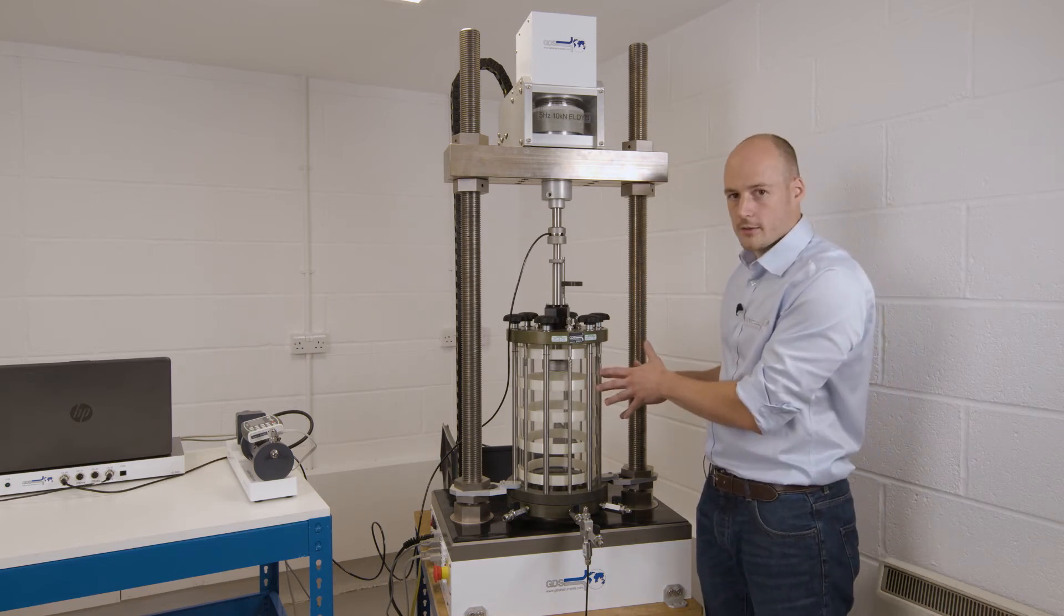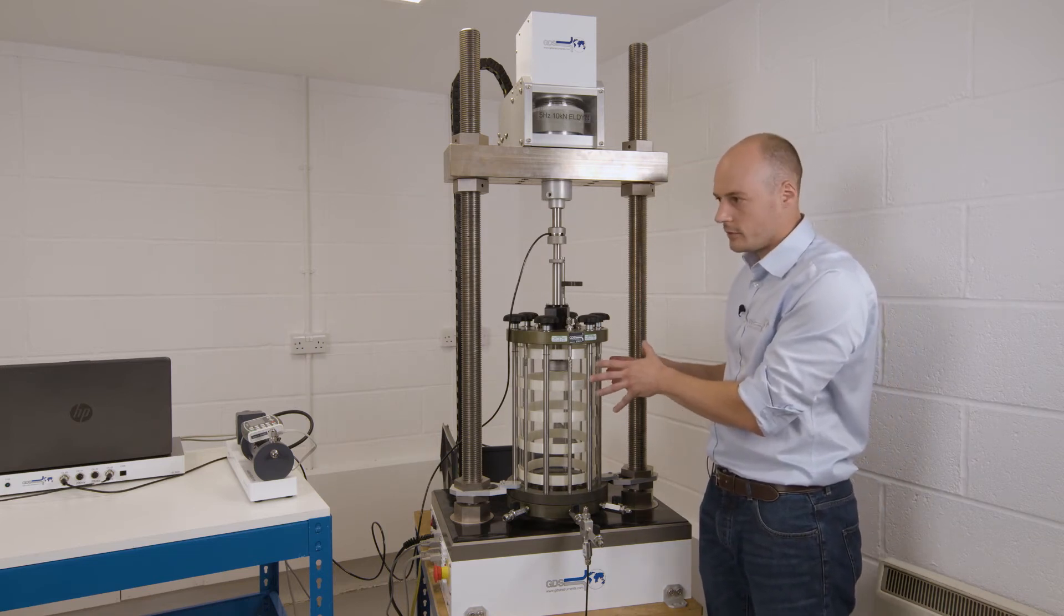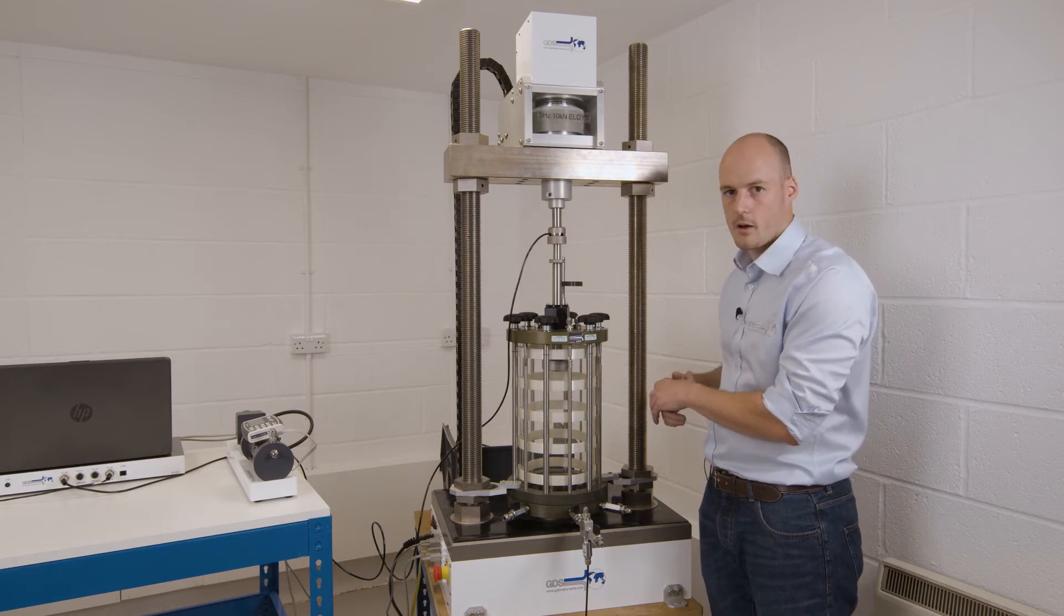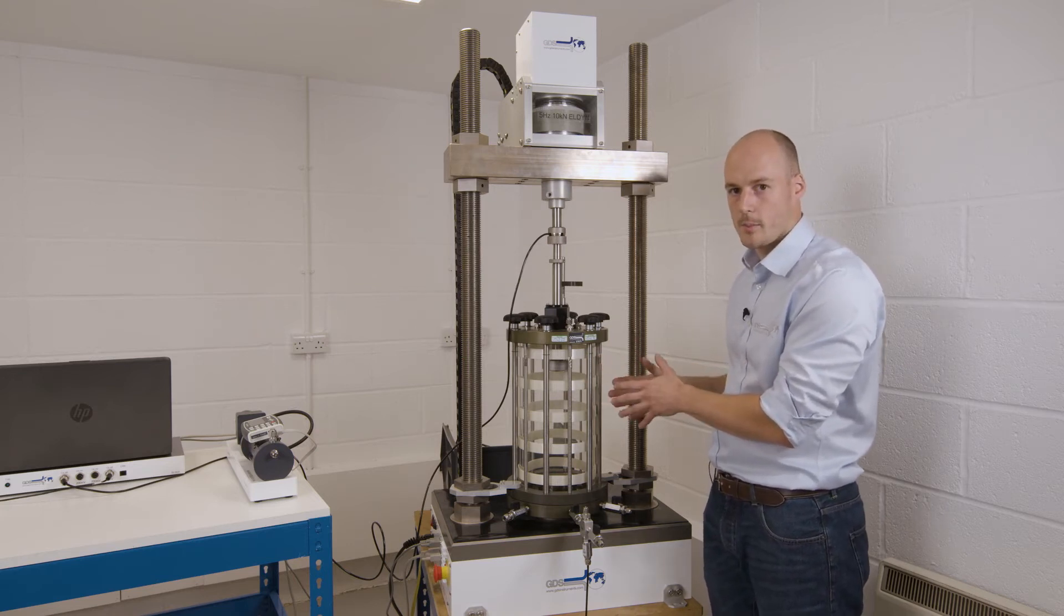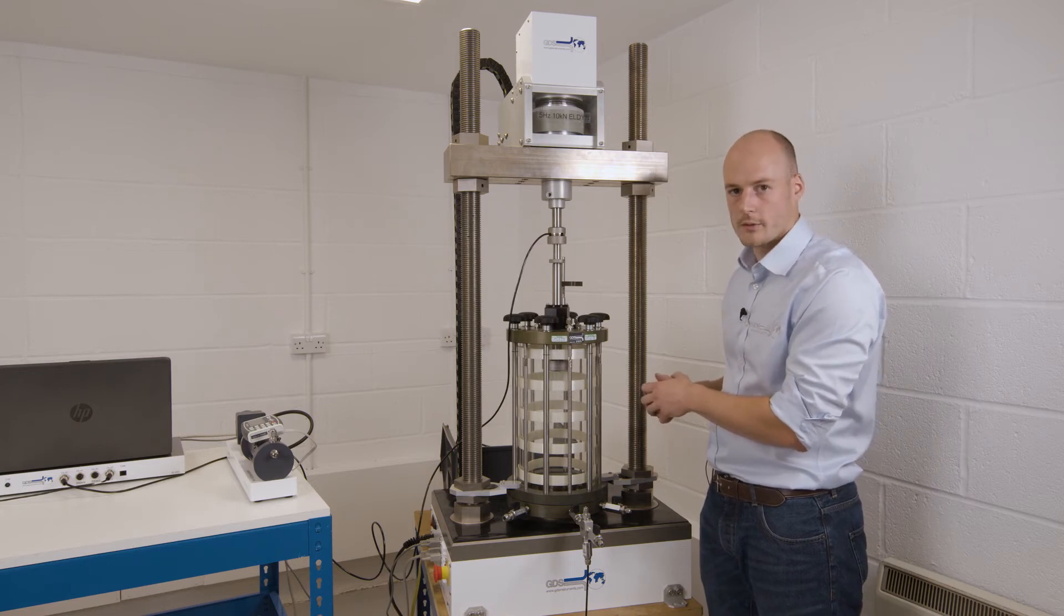The cell pressure provided to the system predominantly is 1MPa, but we can make larger cell pressures up to 2MPa with additional cell pressure controllers.